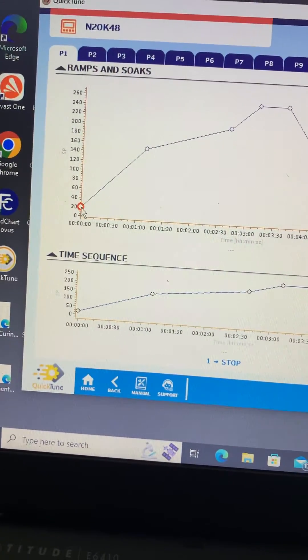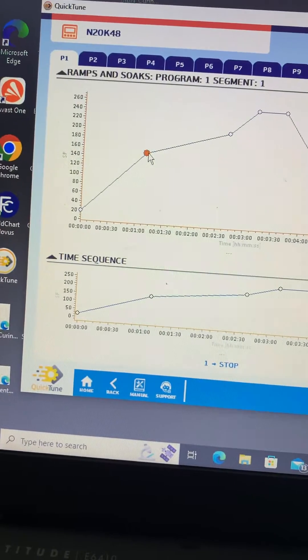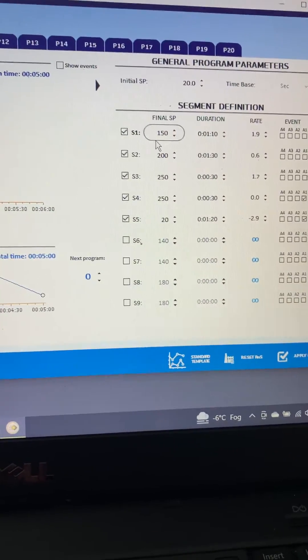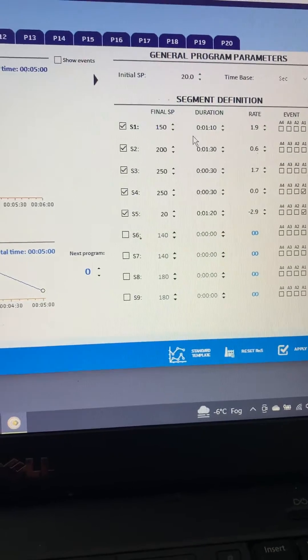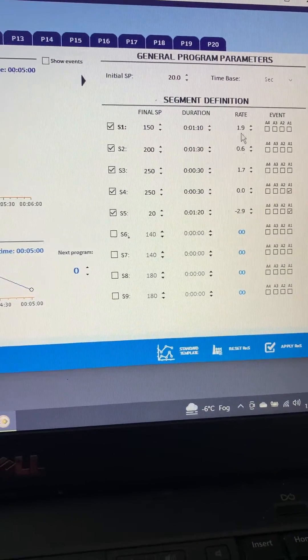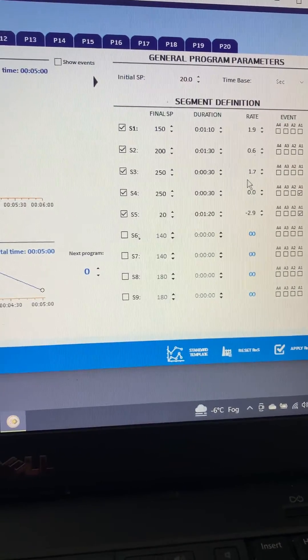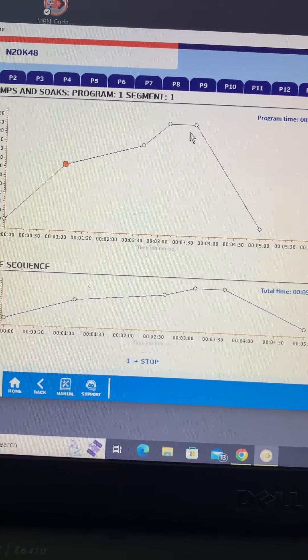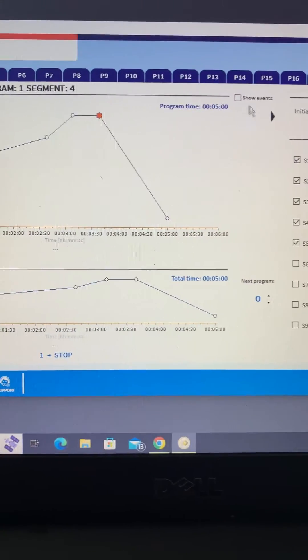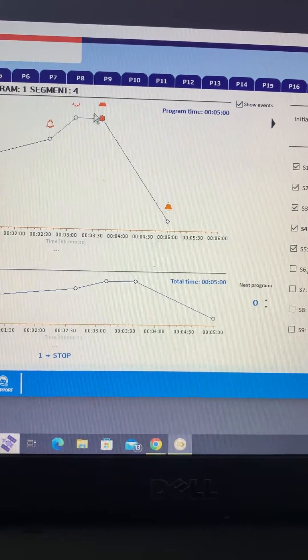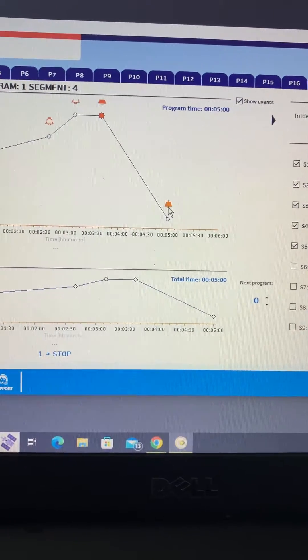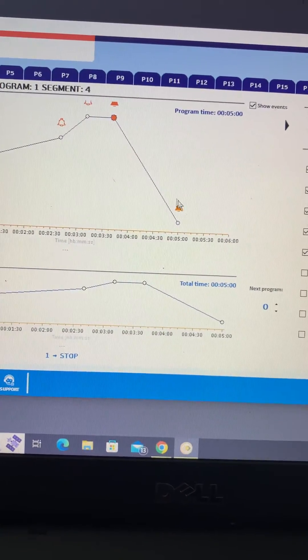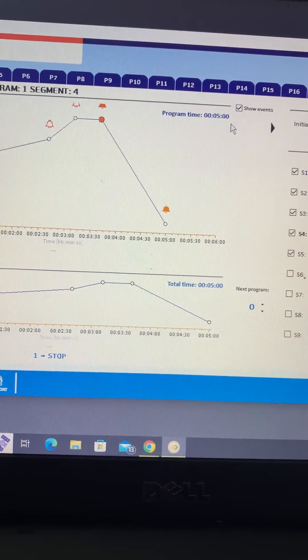If we click here, you can see graphically we're starting at 20 degrees C and jumped across. Our first set point is 150 C and then we've got our duration in minutes and seconds, and it will also show you the rate here. Now what we're doing when we get up to here, if we just click this icon show events, can you see the alarm bell here and here? That's going to bring that relay on and help us to cool down quicker, and the overall cycle time there is five minutes.